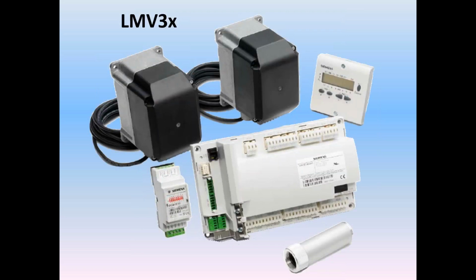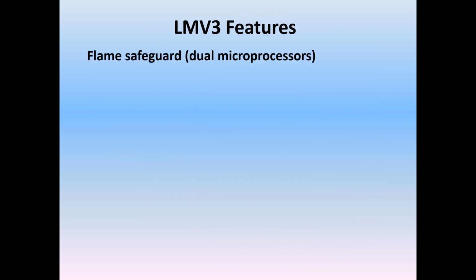Today, we're going to look at the LMV3, the little brother to the LMV5 series, linkageless burner control. You can see a family portrait here. The LMV3 features, it's basically a flame safeguard. It has dual microprocessors as an electronic flame safeguard. It's got 2 parallel programs running, just like the LMV5. It's got a linkageless fuel-air ratio control. It's got a dedicated actuator for air, a dedicated actuator for fuel, and an optional actuator for air control, being a VFD or PWM, and no linkage.